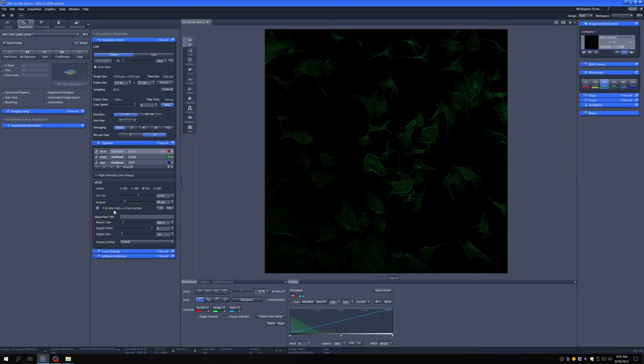And they also depend on wavelength, so they're normalized to wavelength. And then finally, you can see here, this is the equivalent thickness of the optical section with the pinhole set to this size, meaning we did not cut this sample. I just got it in the mail from a company. But if we had wanted to get an image of this kind on a wide field microscope, this is how thin we would have needed to cut it. That's sort of the explanation for what this means.